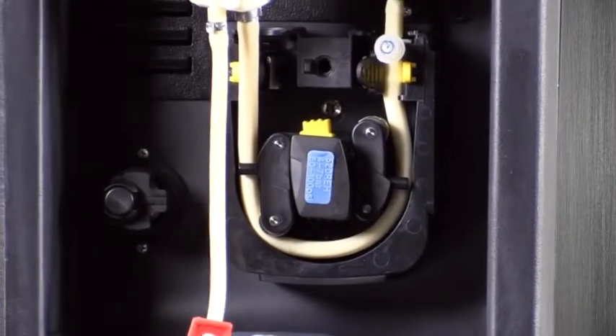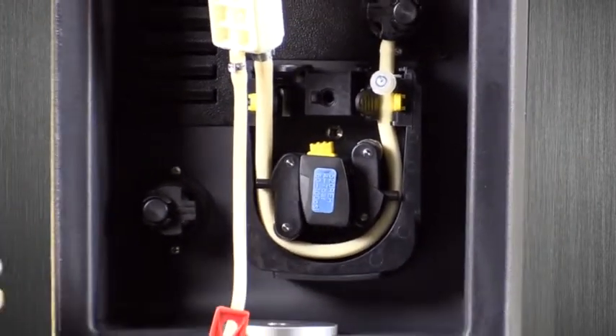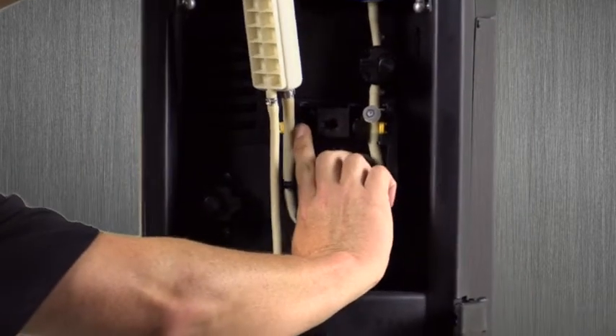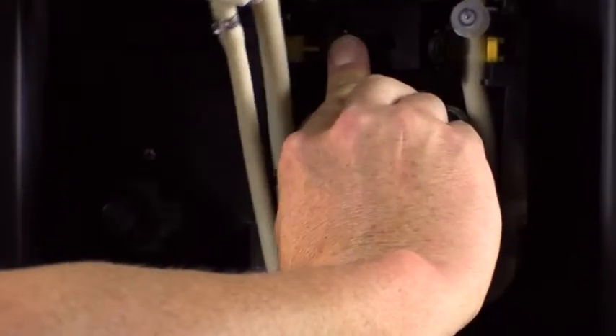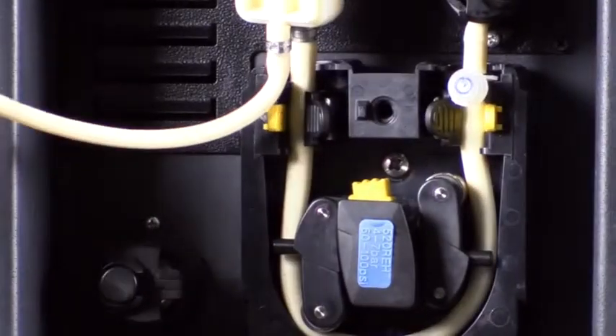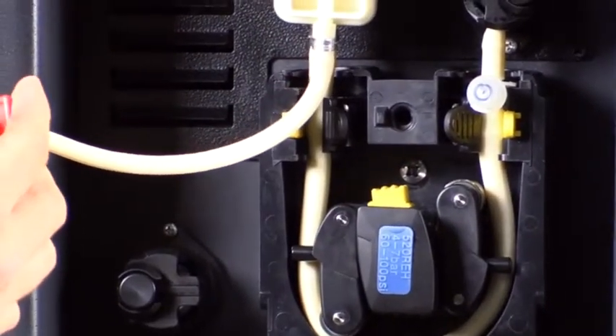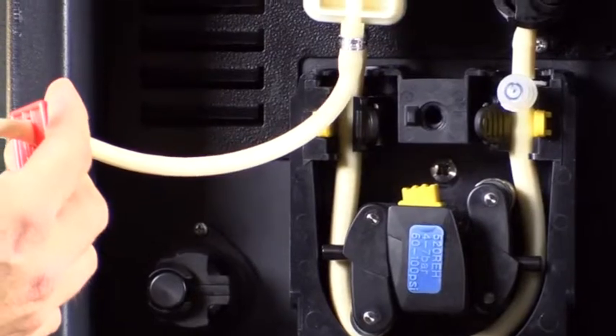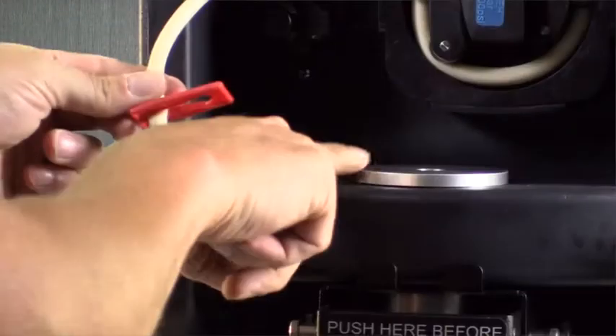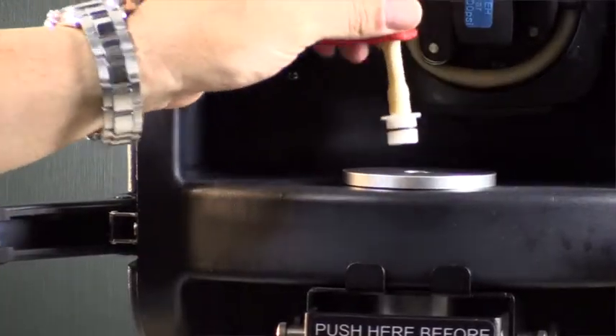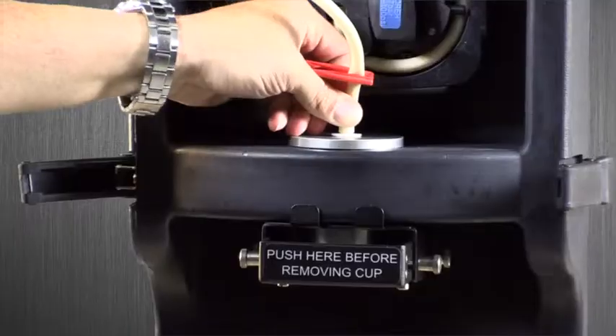Next, duplicate the same steps as shown on the right side by opening the secondary motor assembly clamp on the left side of the unit and loading the final part of the large whip wafer hose into the pump assembly. The next step will be inserting the end of the whip wafer hose into the dispense shield shown here, again making sure that the plastic insert is fully seated.